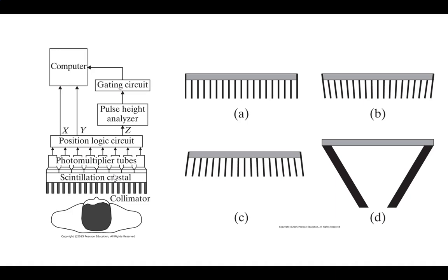So we basically build a logic circuit that will tell when it hit, how big it was, things of that sort. Did it hit a big enough spike that it was a main one as opposed to a scattered one, which will have a different profile. We'll talk about where that goes in. So that's the pulse height analyzer to figure out was it Compton scattered or was it the real thing. It will have a gating circuit which will say, yep, we indeed wanted that, and then it'll let the XY in, and it'll accumulate into the image to build up what's going on.